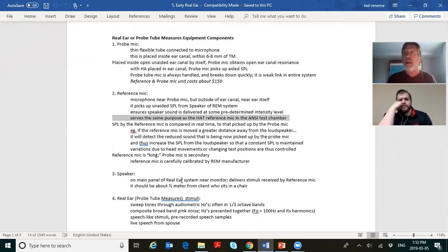And you calibrate a real ear system in the morning to get rid of the effects of the tube in the ear canal. So there's parallels with ANSI testing and real ear measurement testing. ANSI testing, monitor mic. Real ear testing, reference mic. ANSI testing, mic on the 2cc coupler. Real ear testing, probe tube in the ear, that mic. So it's really, and calibration, ANSI, to ensure that the frequency response of the speaker is being flat. Calibration with real ear to get rid of the effects of the tube inside the ear canal.